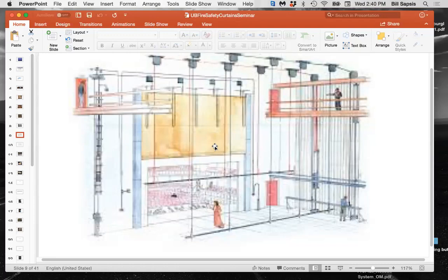Modern theaters, yeah, that's not a problem. Most of the time they get put in properly. You've got an older theater, especially one built before the 1980s, and the anchors used to put those smoke pockets in are going to be just about anything: lead anchors, wooden shields, all kinds of stuff you find in there, because the installers really didn't understand the principle behind them and what they were really doing. You've got an older theater, you're going to want to take a look at your smoke pockets and make sure that they're capable of withstanding the kind of pressure that the fire curtain will put on them. You don't want your smoke pockets falling over and then having the fire curtain flapping in the breeze, right? Because now you just exacerbated the problem. Okay.